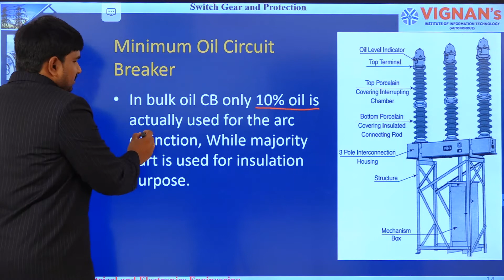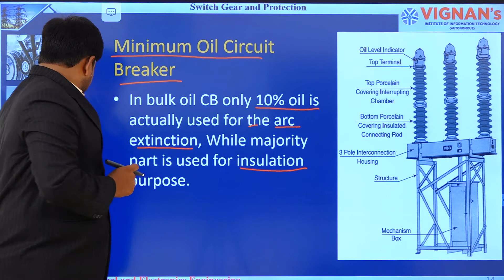So, if you reduce this insulation by providing solid insulating material in the tank instead of oil, as oil has less dielectric strength compared to solids, then by using solids as insulation, the size of the oil circuit breaker will be minimized. That is what we call the minimum oil circuit breaker. Here for insulation purpose we are using solid dielectrics and for arc quenching we are using oil only. How we quench the arc is the same as in bulk oil circuit breaker.